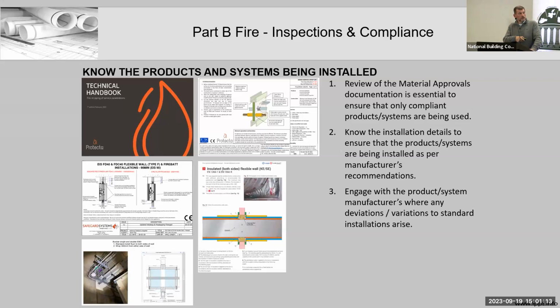Typical details for the installation of fire dampers, typical details for fire-related ductwork. There's a very specialist one for fire stopping detailing in relation to electrical busbars, where there are very few manufacturers or products that can actually deal with that and fire stop it properly. It's a unique one, and we know that because when we went looking for it, we couldn't find it. We had to scour Europe and find a German manufacturer of a fire stopping product that had the relevant details to give us the 90-minute and 2-hour fire resistances we needed.